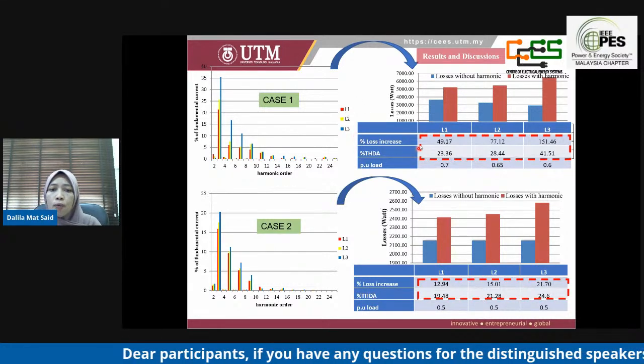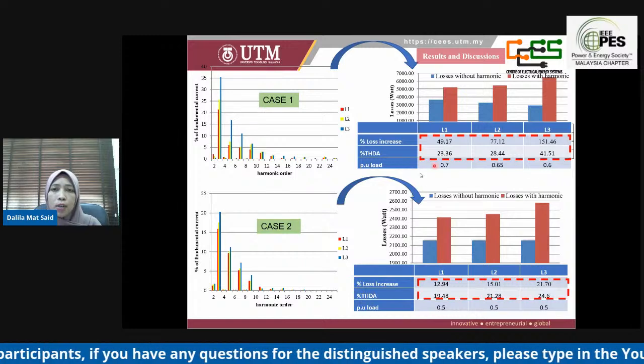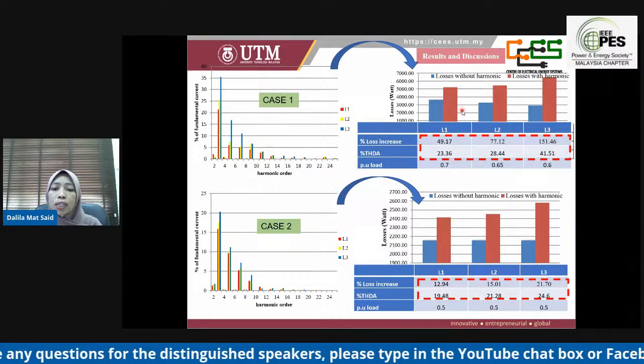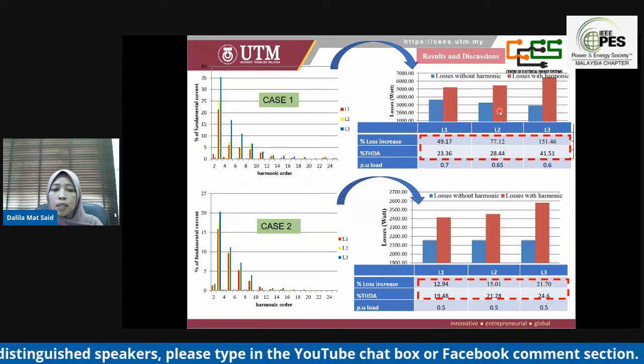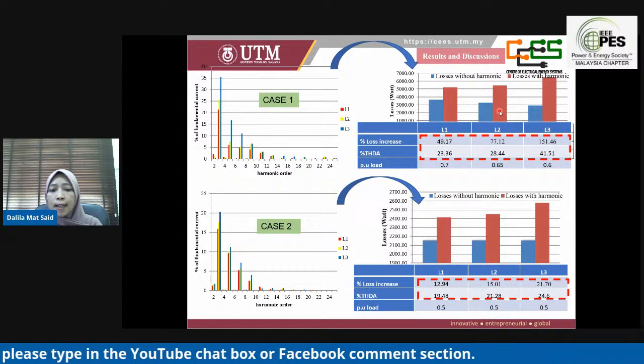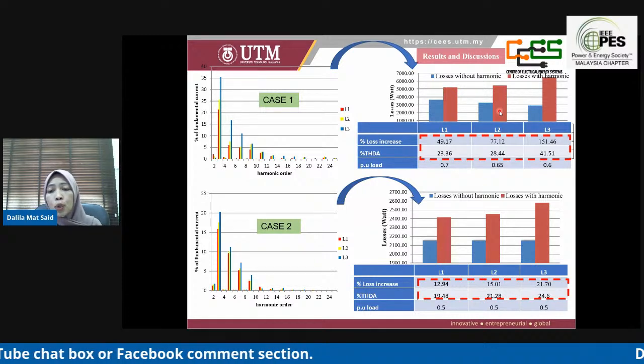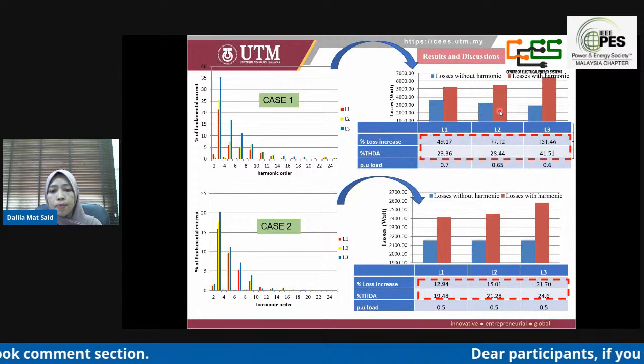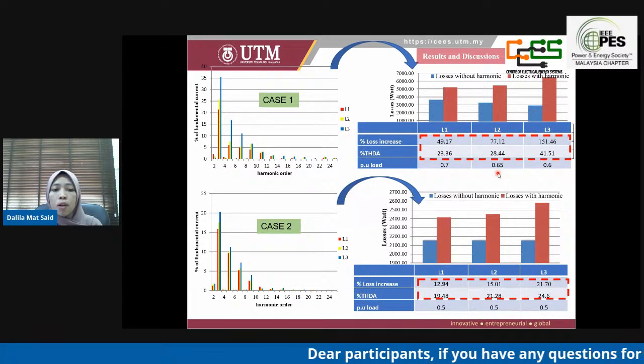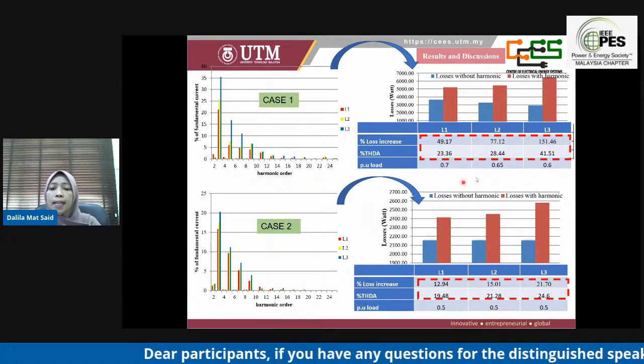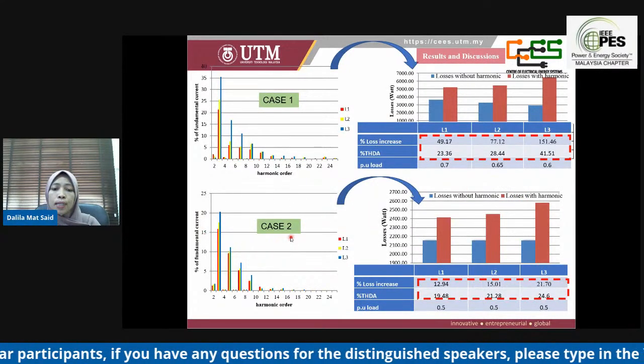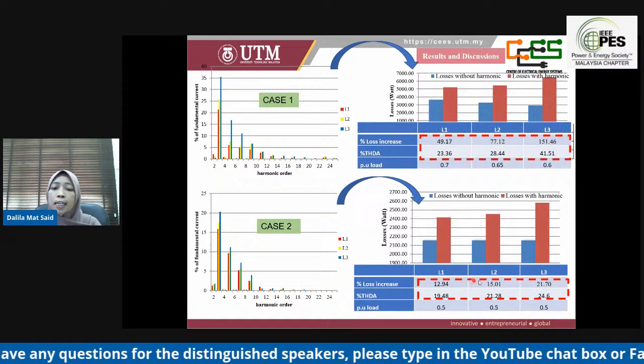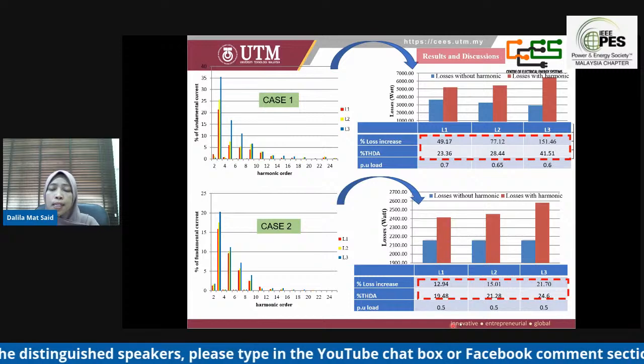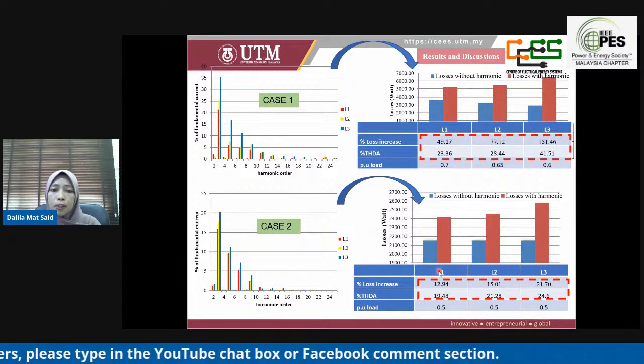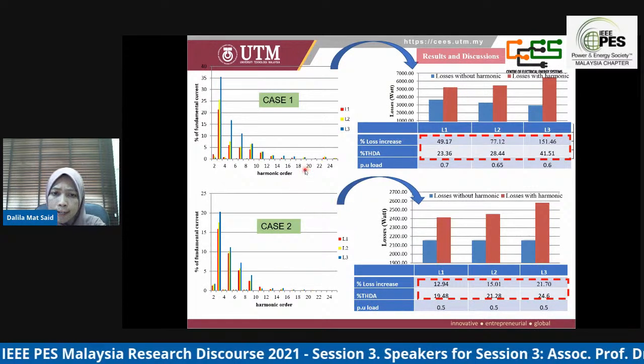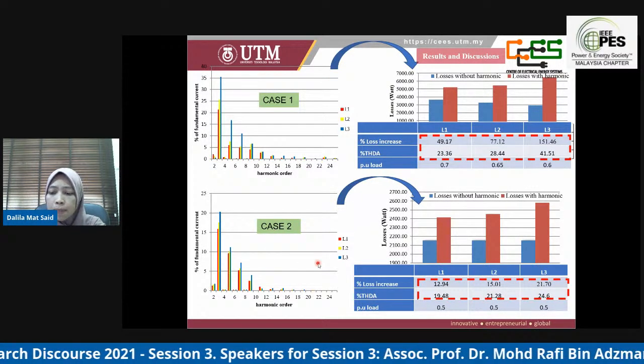In the first case, we consider different per unit loading for different total harmonic distortion for current. Based on the analysis, we can calculate the percentage loss increase due to this harmonic. From the result, losses with and without harmonics can also be classified clearly. And case 2 here is an example for different harmonic distortion with the same per unit loading. There are two cases here: the first we can consider as high harmonic and the second as medium harmonic.